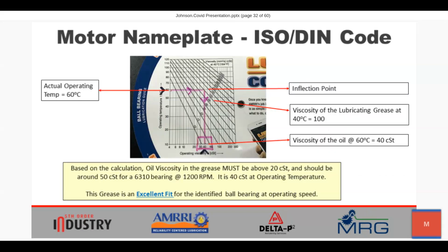Further, on the back side of this calculator, we can validate that the product in use is the correct product or the best fit product. We know that we needed at least 20 centistoke and preferably 50 centistoke from the viscosity of the lubricant used to care for the bearing.